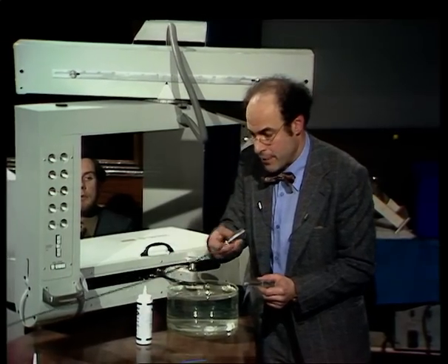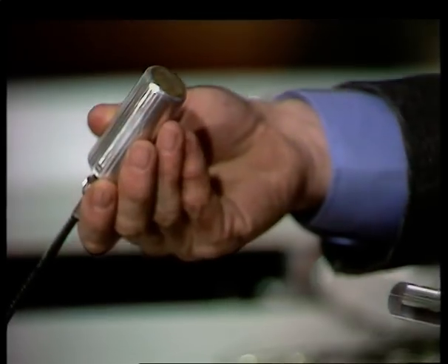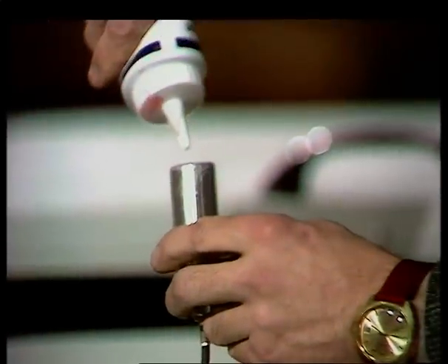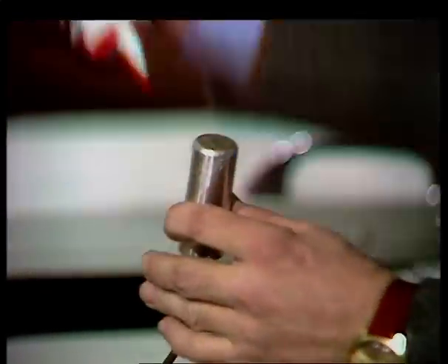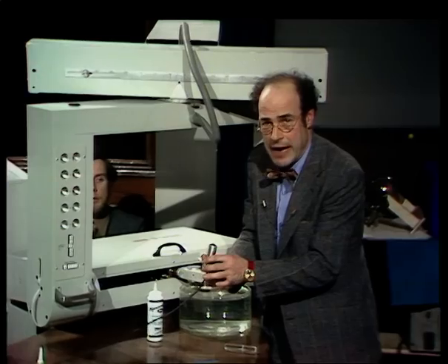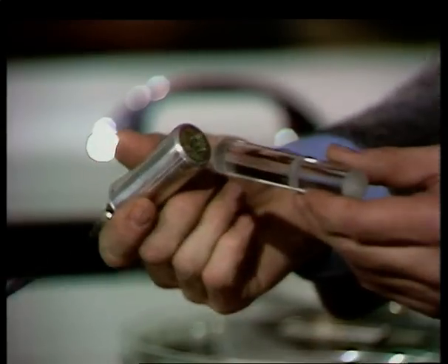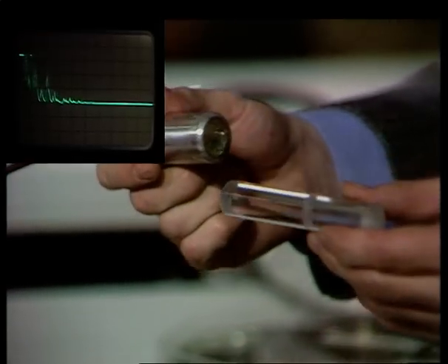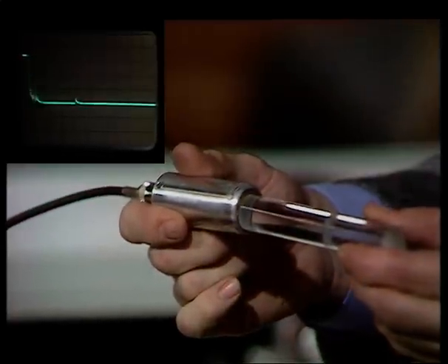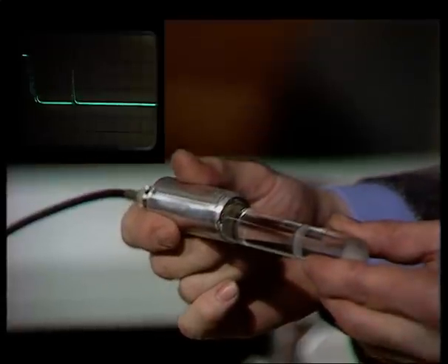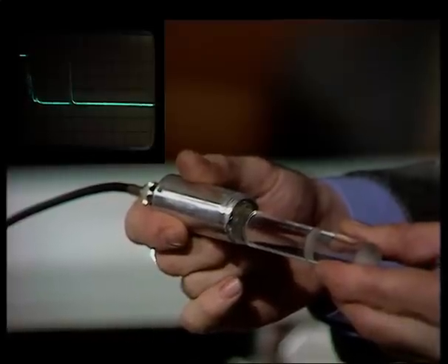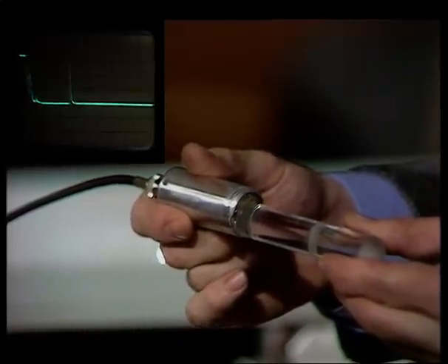I've got an ultrasonic probe here, which sends out pulses at a much higher frequency than the ones you heard just now, but nevertheless, the principle is the same. You will remember that when I used ultrasound on myself, I used a coupling medium because this high-frequency sound doesn't like traveling through air very much. I'm going to apply it to one end of this rod so that sound pulses are now going into the rod, being reflected by the imperfection and coming back again. And we're going to look at our now familiar cathode ray tube beam. And you see that there's a big dip at the beginning on the left, which is a pulse setting out.